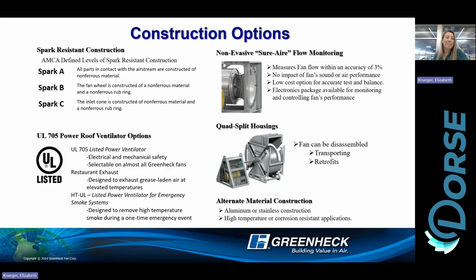When test and balance comes out, they drill holes in the ductwork, or they put probes in a really weird spot in the airstream, and their measurements don't come out to be what the fan is actually doing. So all of our fans are AMCA certified, so we know what our fans are going to do. And I'll talk a little bit more about AMCA certification here as well.